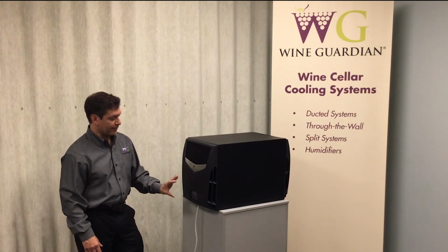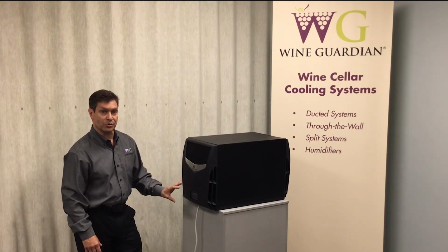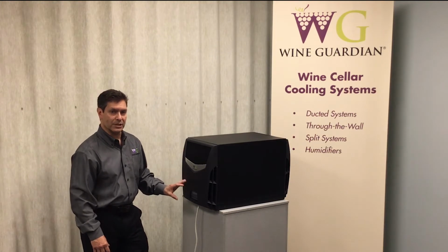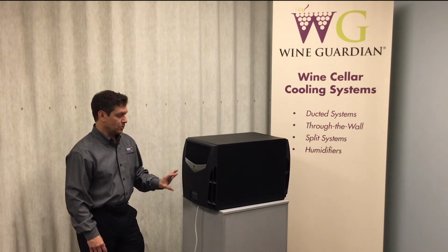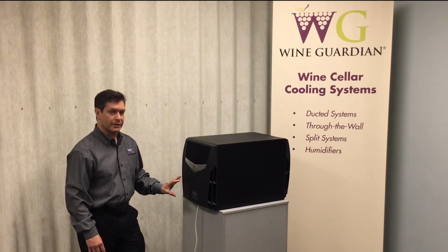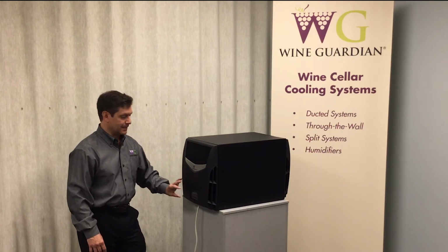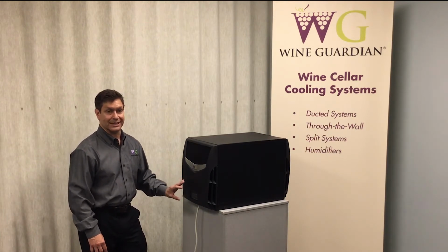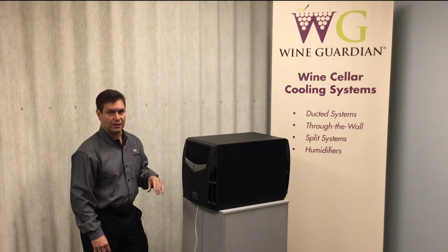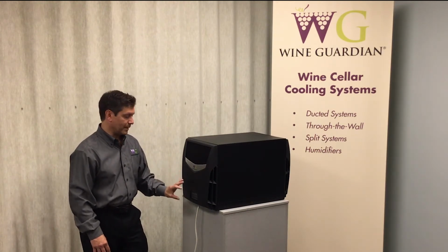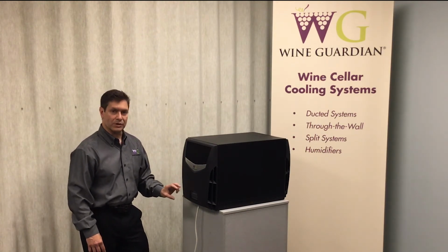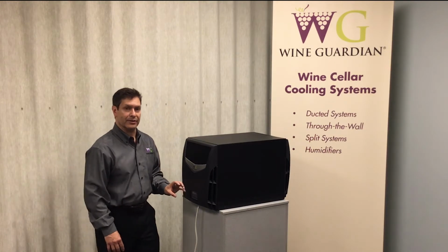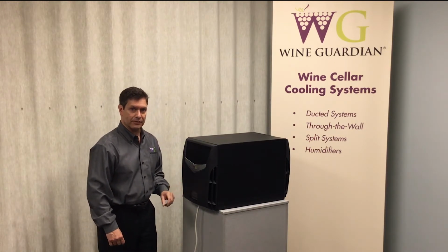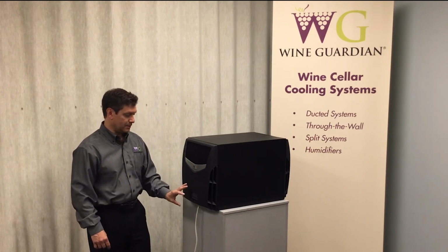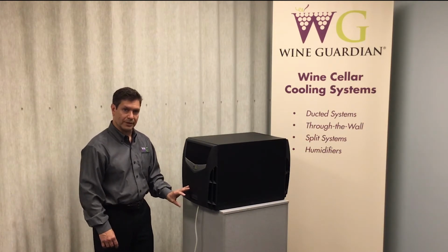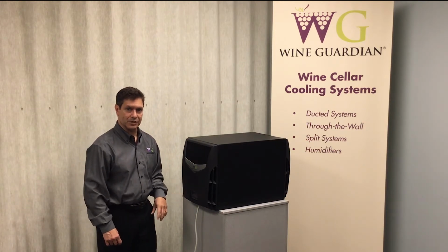You usually want to have this accessible to you so you can see what's going on with the unit and your room. You don't want to install the unit in an area where you can't see the control panel or it's difficult to access. Maybe it's too high in the room or over in a corner. You want to be able to see what's happening in the area and in the wine room itself. So this is the area that you're going to view to determine what the temperature and humidity is of the space.